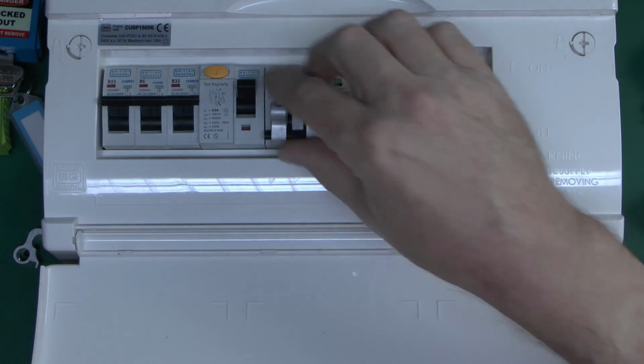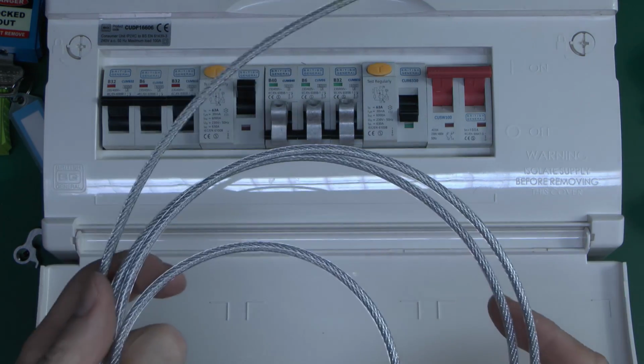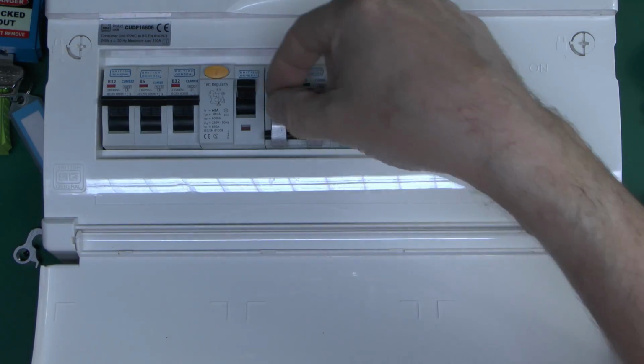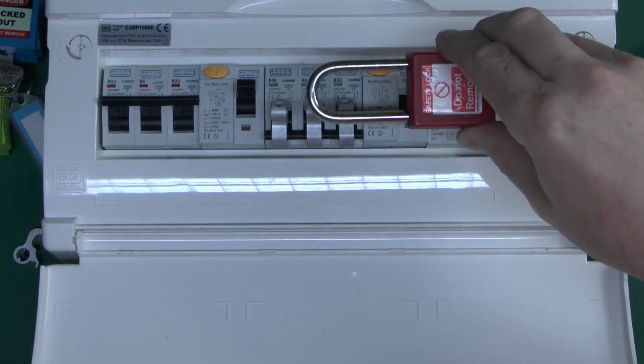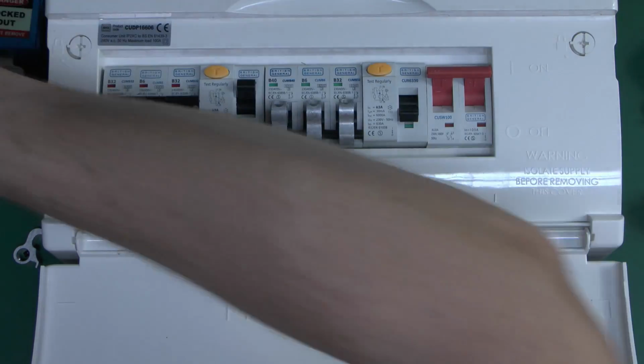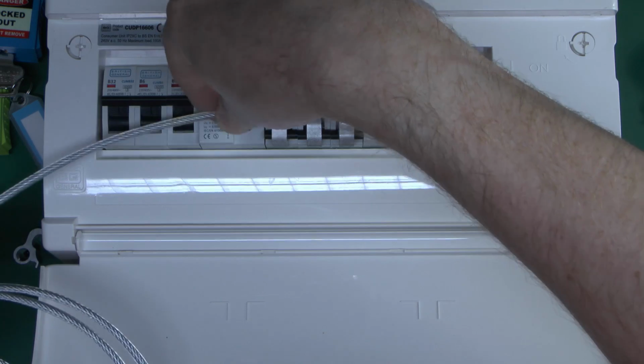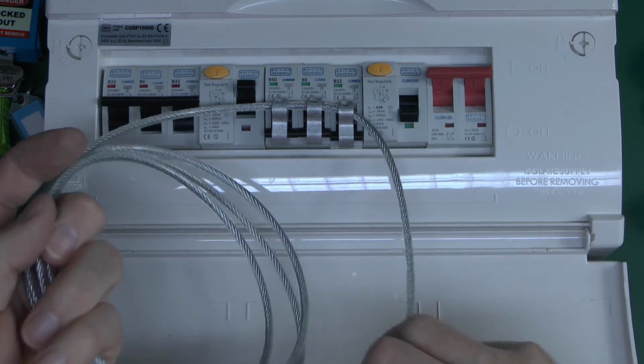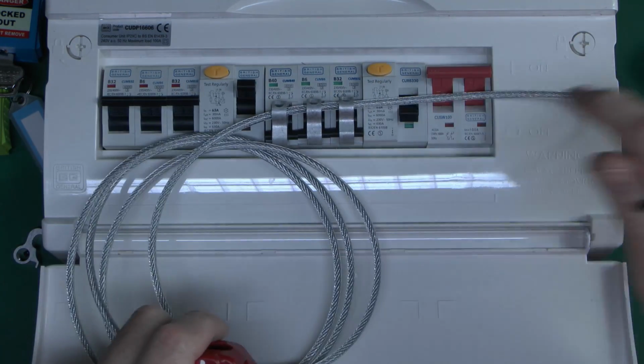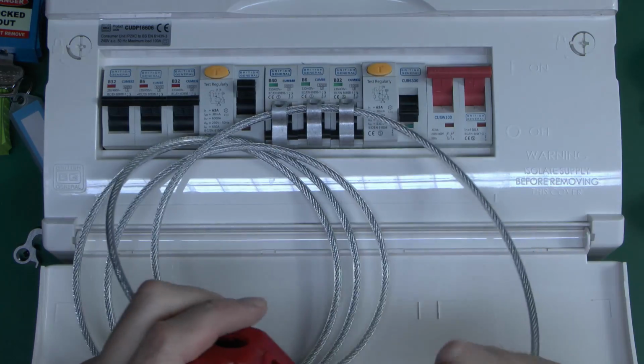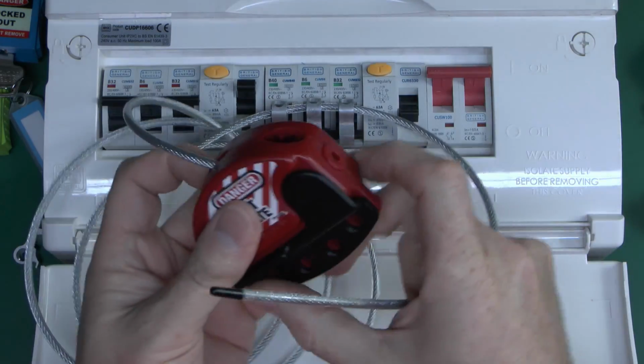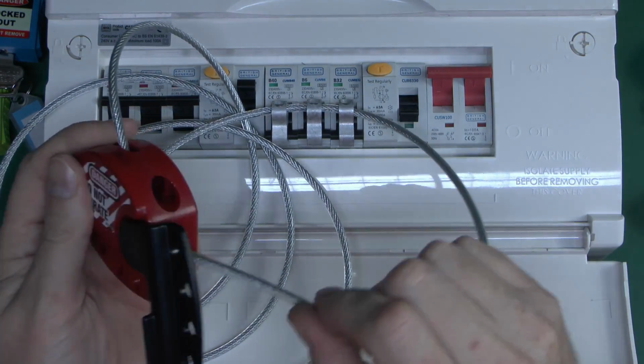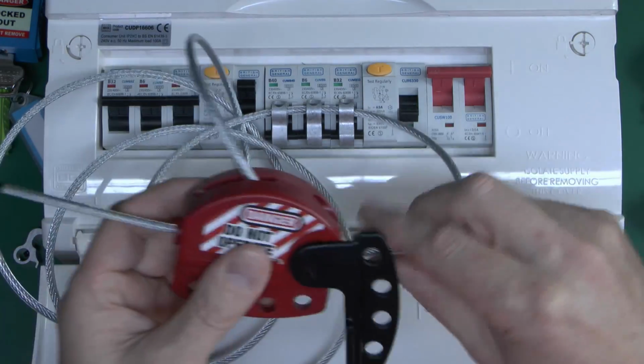Now for multiple circuits, say all three of these, that's where this cable job comes in. Rather than trying to fit a padlock through all three, which won't work because it's not long enough, what you can do is get this cable and shove it through all three. That prevents access to the screw to undo it. The end of the cable goes into the hole like that, and it goes through perfectly easily.